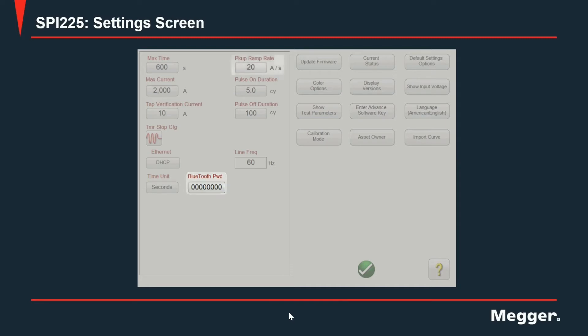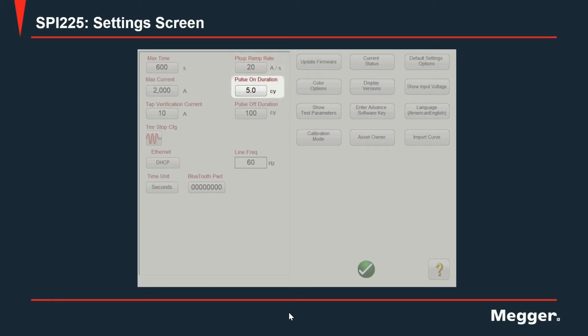Next, we have pickup ramp rate which by default is set to 20 amps per second and is for the user to change the rate of change of the output when doing instantaneous testing. In conjunction with the next two settings, the first being pulse on duration, that again whenever the unit is testing instantaneous elements of the circuit breaker automatically, it will use this pulse on duration to count the time the output is energized on those pulses used in this test mode.